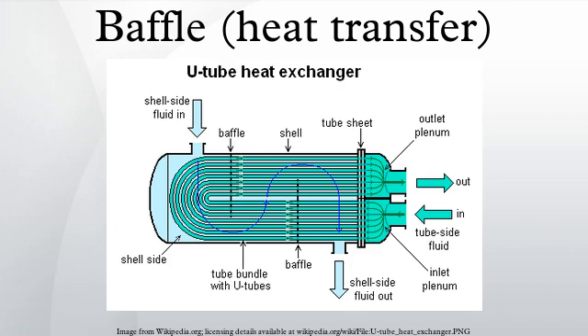The main roles of a baffle in a shell and tube heat exchanger are to hold tubes in position, both in production and operation; prevent the effects of vibration, which increases with both fluid velocity and the length of the exchanger; and direct shell-side fluid flow along the tube field.